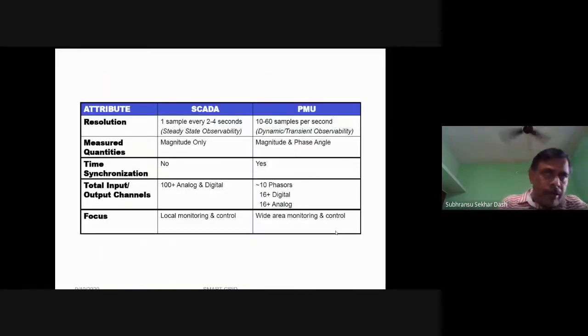So there is always a comparison between SCADA and PMU. In terms of resolution, PMU has very good resolution. SCADA measures only magnitude, whereas PMU measures magnitude and phase angle. The comparison is like one is an MRI scan and the other is an X-ray. The X-ray is nothing but SCADA, and the MRI scan is PMU. So depending on applications, you can go for PMU. PMU may be costlier than SCADA. Where the requirement is there, you can go for PMU.